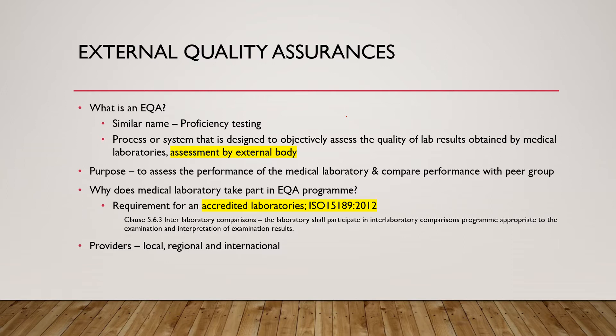Medical laboratories take part in an EQA program because this is a requirement for accredited laboratories under ISO 15189:2012. In clause 5.6.3, it states that inter-laboratory comparison is compulsory and labs shall participate in an inter-laboratory comparison program appropriate to the examination and interpretation of examination results. The lab can join EQA programs that are available locally, regionally, and also internationally.